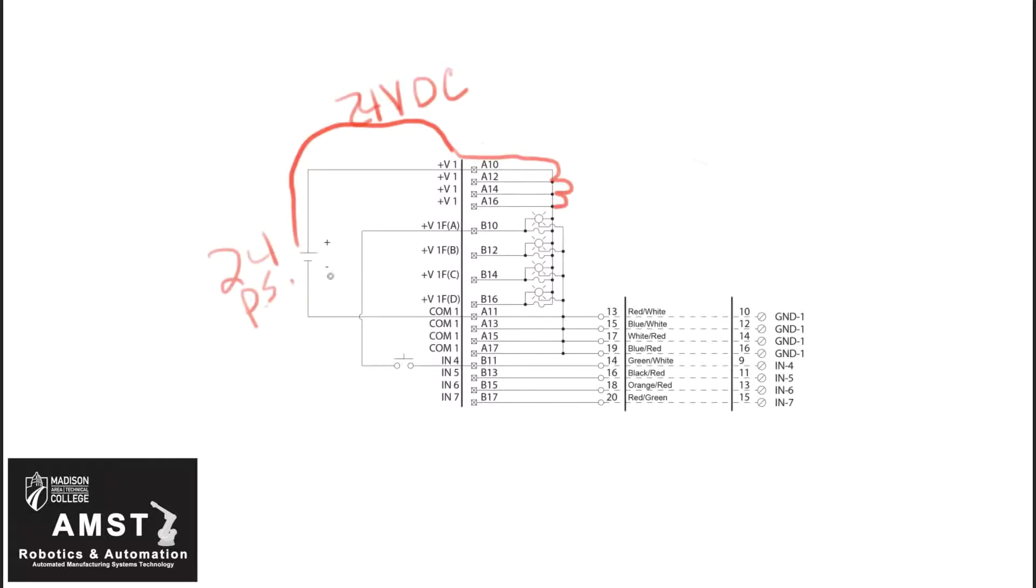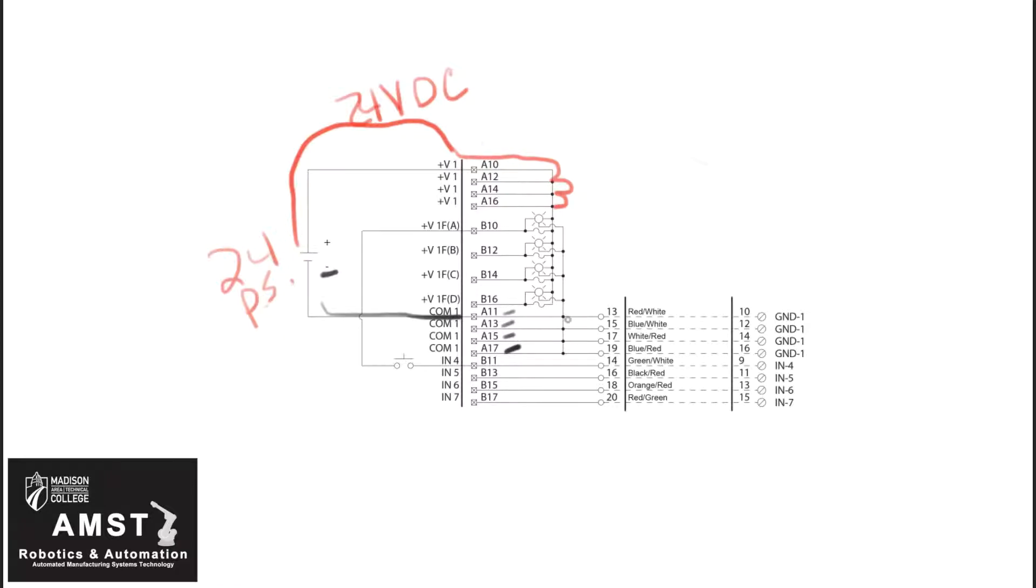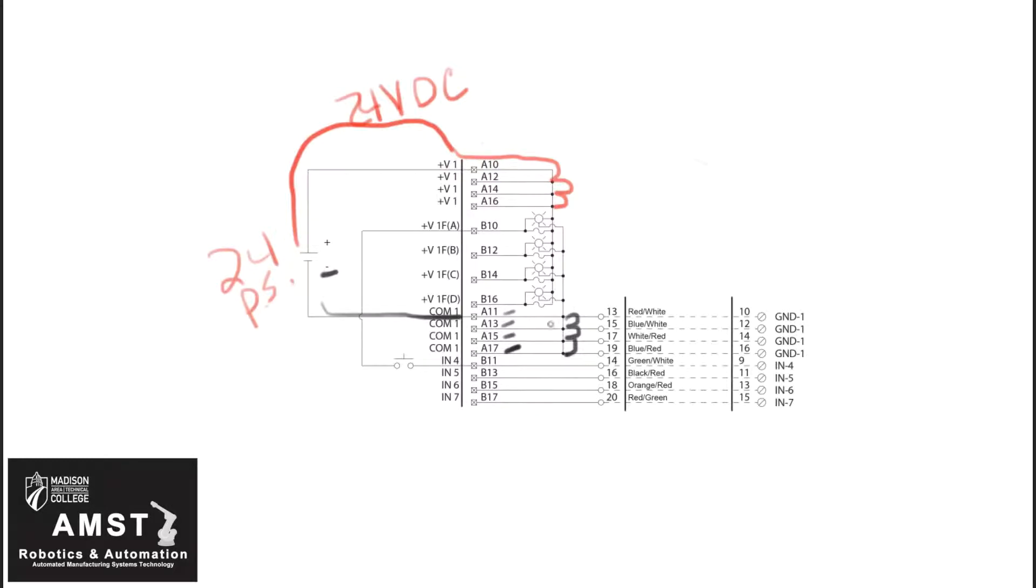Now let's take a look at the negative side of the power supply. It's going to connect to COM1 or terminal screw A11. A11 is also jumpered to A13, 15, and 17. So one negative wire to A11 really takes care of A13, 15, and 17. With just two wires, our 24 volt power supply connected to positive A10 and negative A11, we're taking care of eight of our 16 terminals.